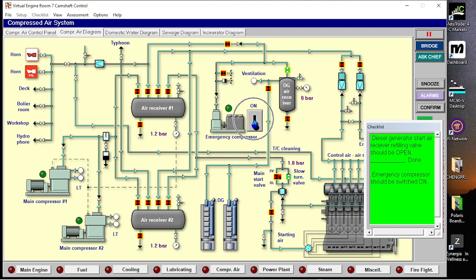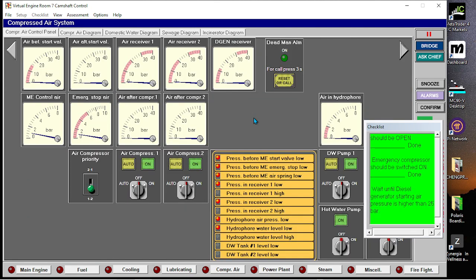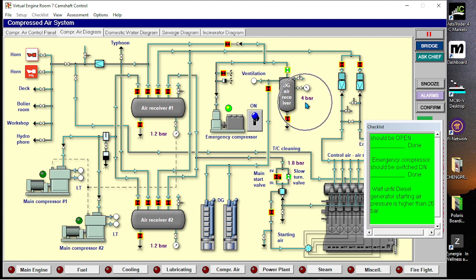So we will switch on this emergency compressor. Wait until the diesel generator starting air pressure is higher than 25 bar. And we will wait for this gauge of the diesel generator receiver until it reaches 25 bar. We can also check the pressure here. As you can see, the pressure now is 5 bar, and we will be waiting for this until it reaches 25 bar.